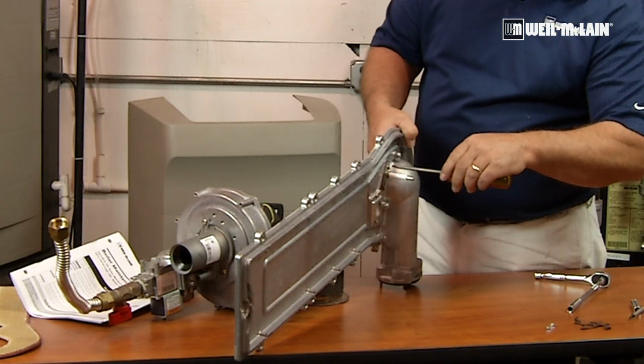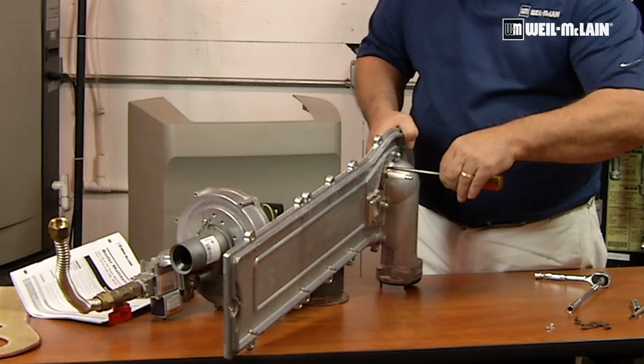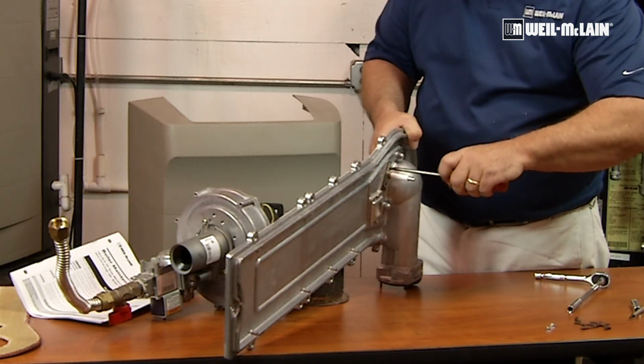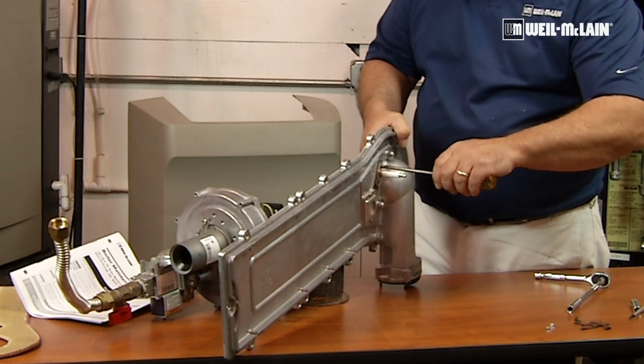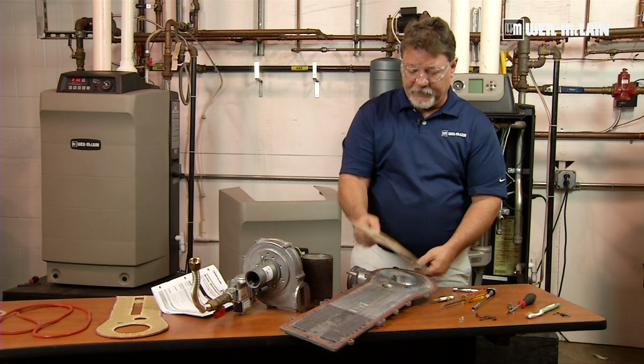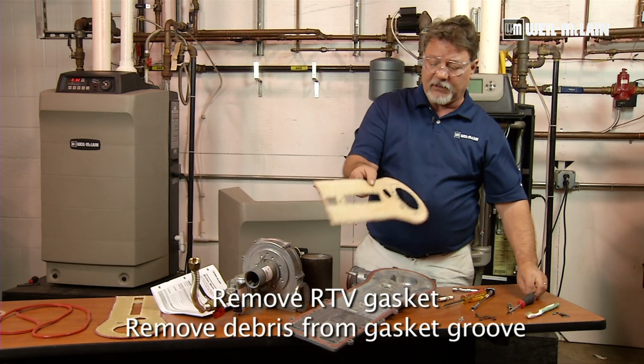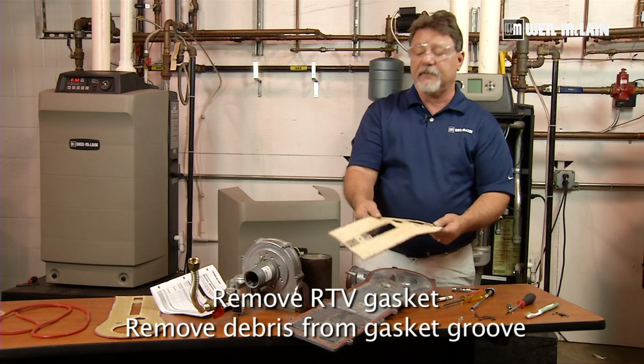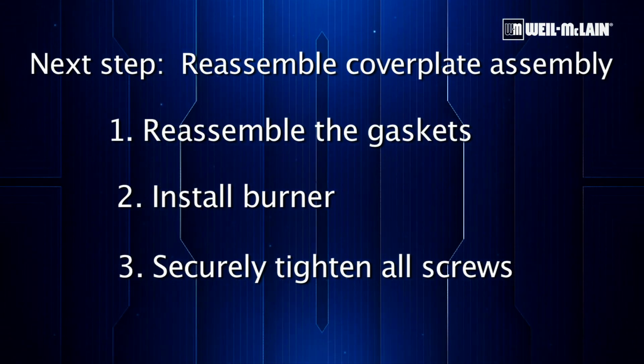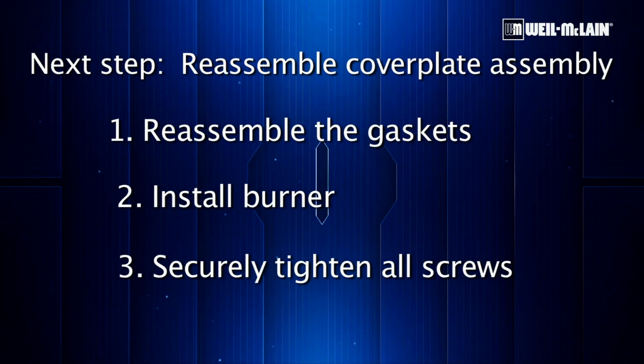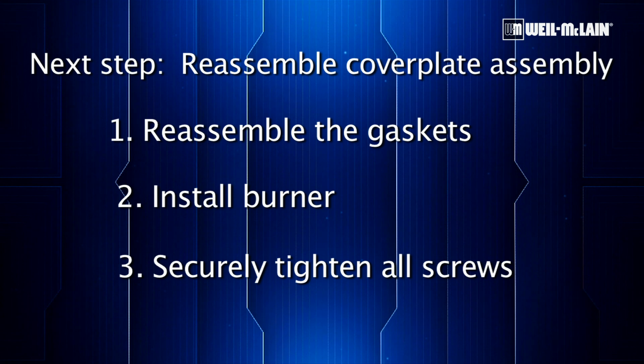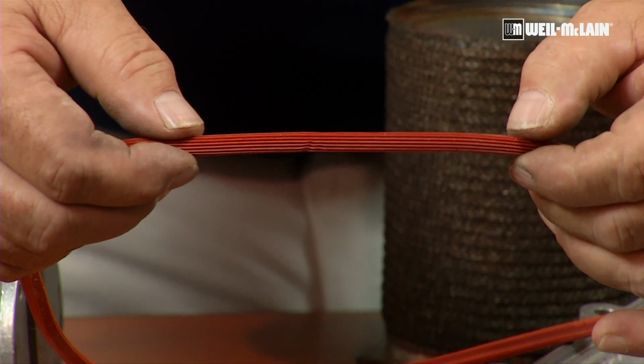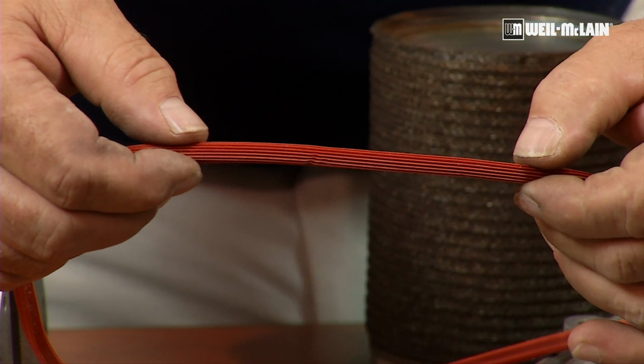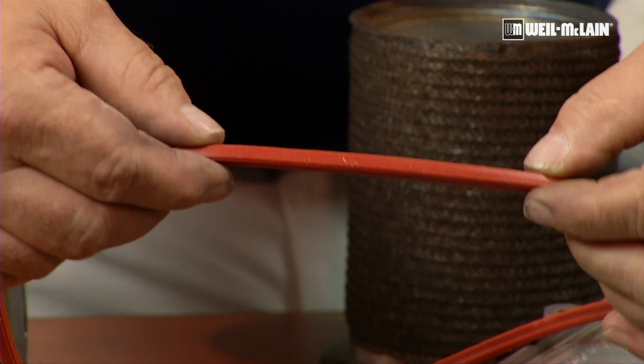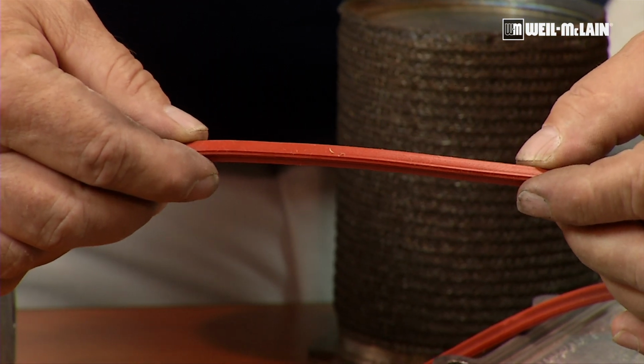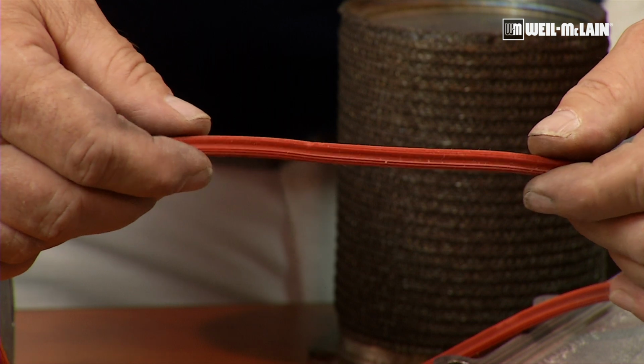At that point, and you can do this earlier as well, I don't think there's any real time frame here, but what I'm doing is I'm removing the igniter. Now we simply remove the insulation and discard it. I'm going to take the gasket and reinstall the new gasket. The top side of the gasket is ribbed. The ribbed surface faces upward.